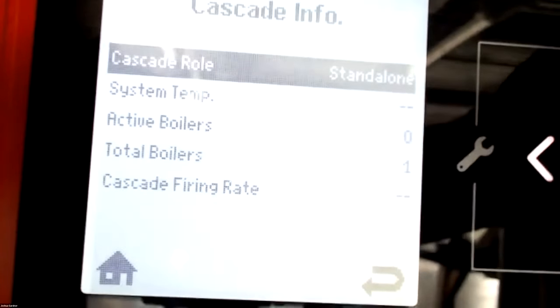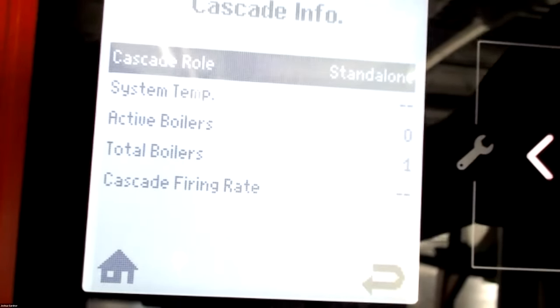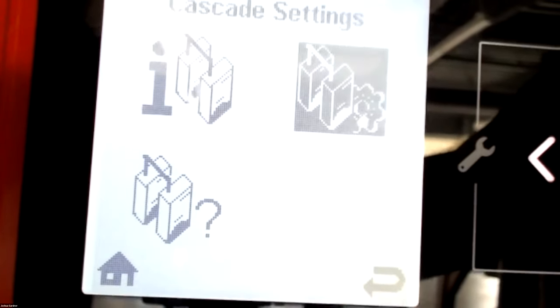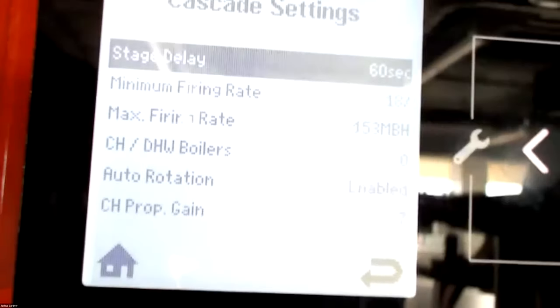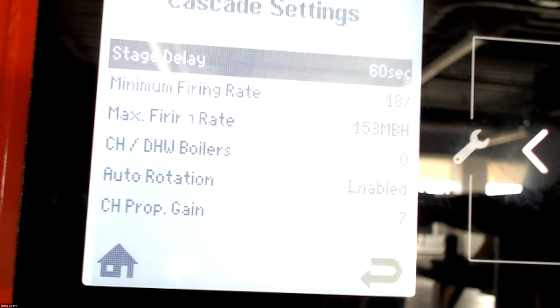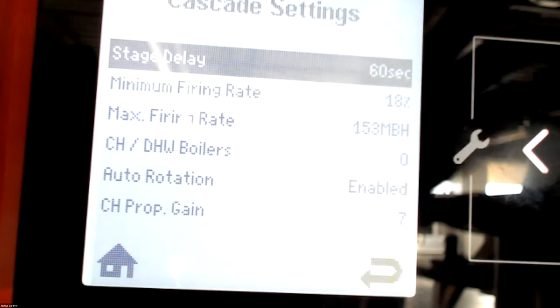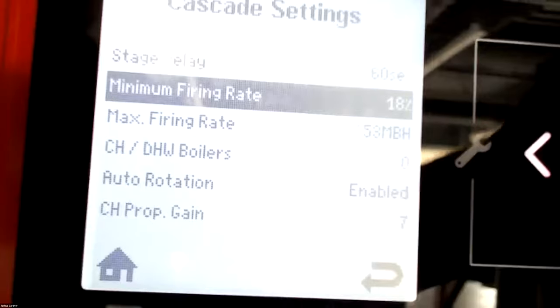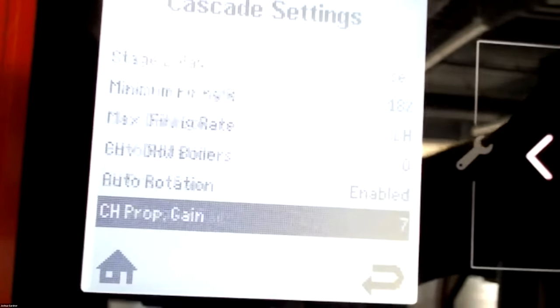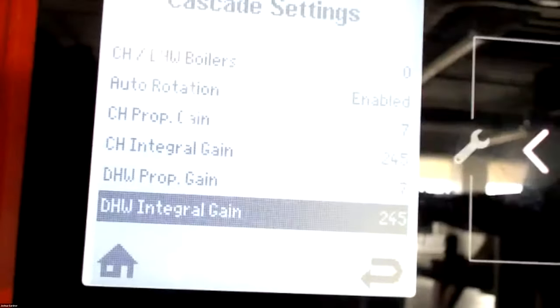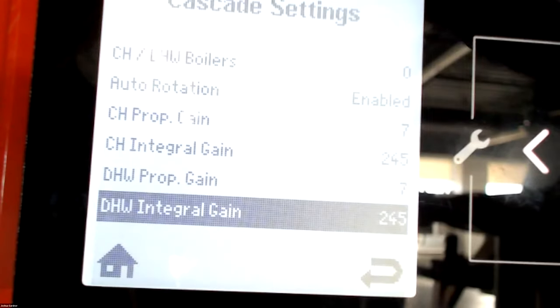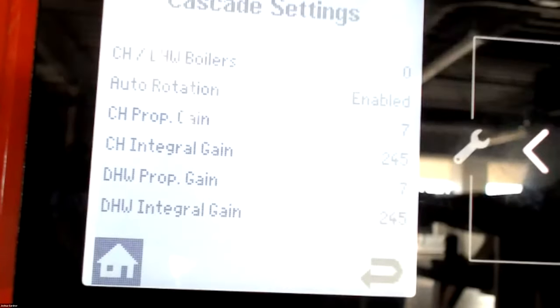Let me go into the cascade. So you'll have your cascade info. This is not set up, so there's a bunch of information that you won't see or we can connect to. Cascade settings. So you'll be able to set your stage delay, your minimum firing rate, your max firing rate, how many CH central heating and DHW boilers you have, your auto rotation, your gains, proportional and integral. Those on the CH and DHW, only adjust those if you call us.